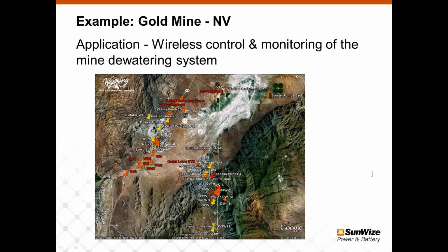Several different methods were used to retrieve the data. There were 3 different areas, each with a redundant master, all Allen Bradley equipment — ControlLogix 5000 redundant controllers at each master, with 1734 point I/O out in the field interfacing to various sensors for pressure, flow, and valve control, plus VFD pump and motor controls to move the water.